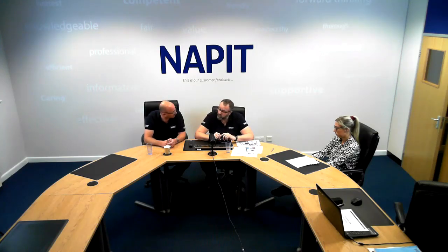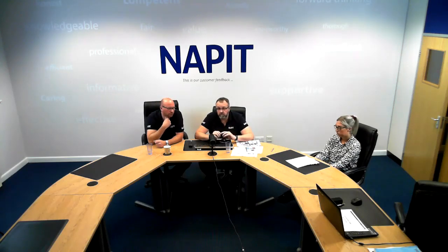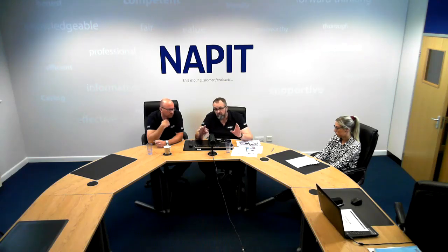Would you agree, Rich? I would, yeah, absolutely. Obviously if you're going to supply another consumer unit and you already have one RCD up front, as we've spoken about, it kind of scuppers your division of installation down. So when you start splitting your circuits down, you've only really got the amount of leeway from your upfront RCD, which isn't very good. So avoid it if you can. If you can't, you've got no options - try and do something else, upgrade the size of the RCD if you can.